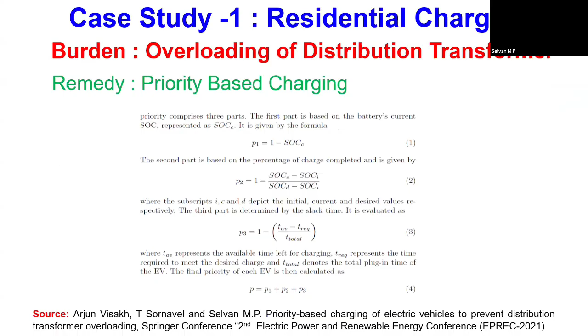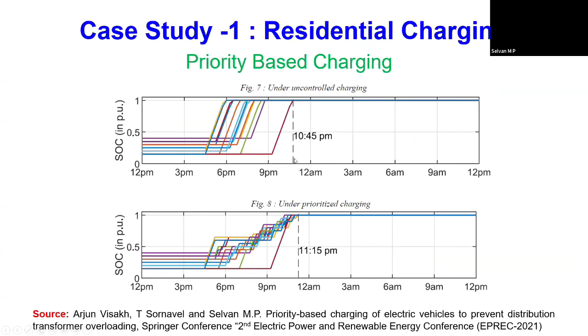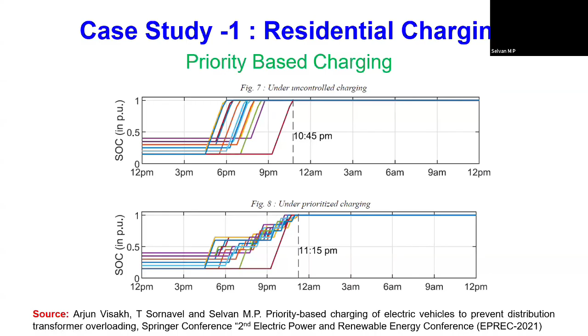So when we do that priority based charging, overloading on the transformer can be well limited. And of course there is not much difference. Without priority, all the customers charged their vehicle at 10:45 p.m. Here only 30 minutes extra happened. During those 3 hours where the transformer got overloaded in uncontrolled charging, in controlled charging the transformer overloading is avoided. The charging is done in a priority based manner so that all the customers are charged to full capacity with only 30 minutes delay. It is not a major problem in this case study.